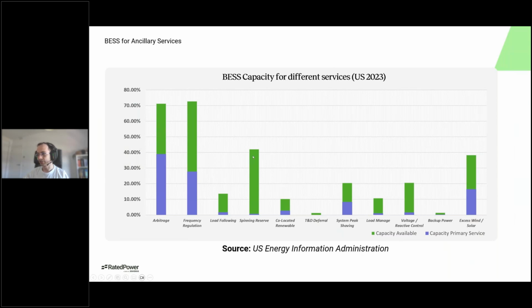We see here that spinning reserve is also provided by a lot of them. And also we see a big importance in wind and solar penetration. So this is why co-located renewables and excess wind and solar is also important. If we check the purple ones, which is the primary objective of the battery, this means each battery system will have a primary objective. We see that arbitrage and frequency regulation are the two main focus of battery systems, and also co-located renewable and excess wind and solar is gaining importance. For example, spinning reserve, even though many batteries can provide this service, almost none of them is primarily focused at this service.